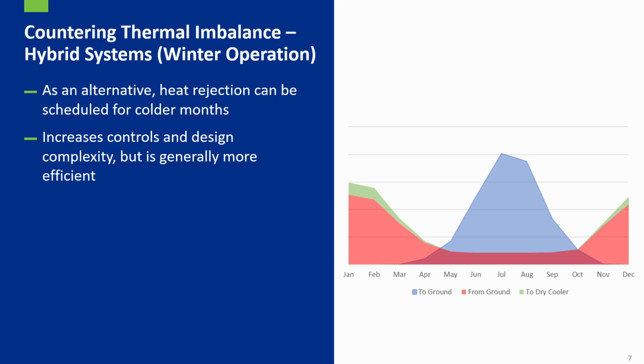Another, potentially more efficient, approach is what we call winter operation. This applies to a cooling dominant system, but it's really more of a peak shifting than a peak shaving strategy. If you have a hybrid thermal resource that relies on outdoor air to reject heat, rather than rejecting that heat in summer, when it's very hot and you'd need to run your loop very hot, you instead run your thermal resources in winter. You track year-round the total net BTUs going into and out of the ground.